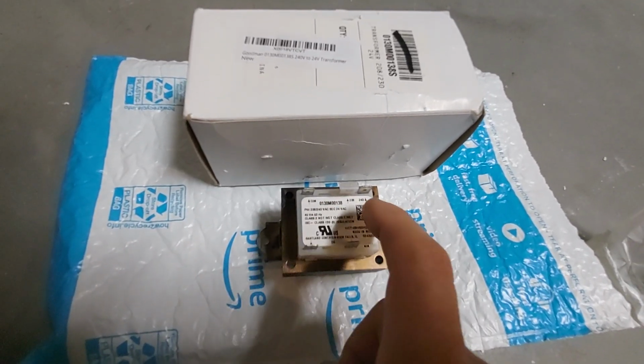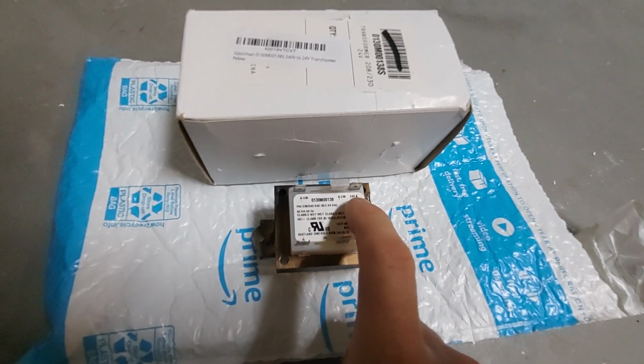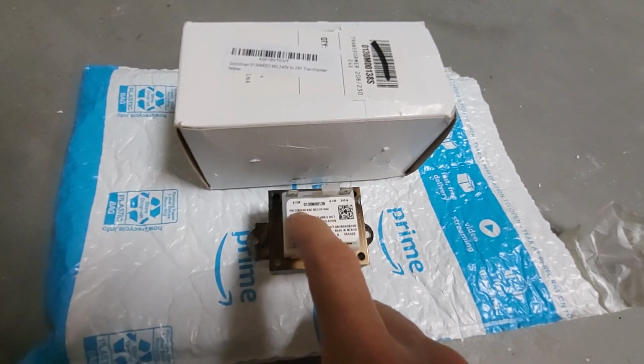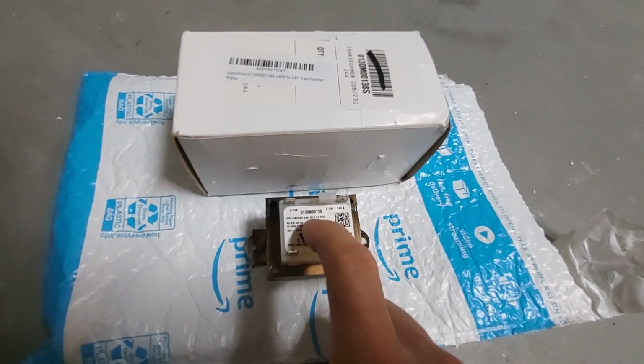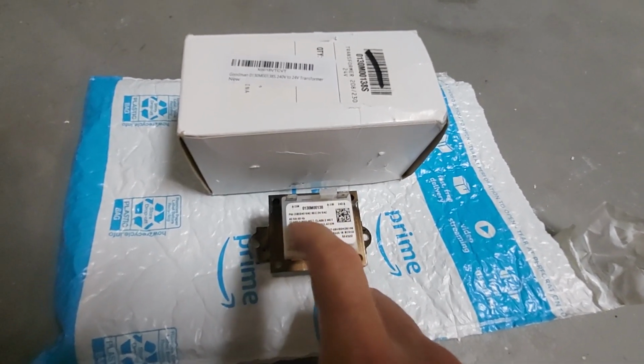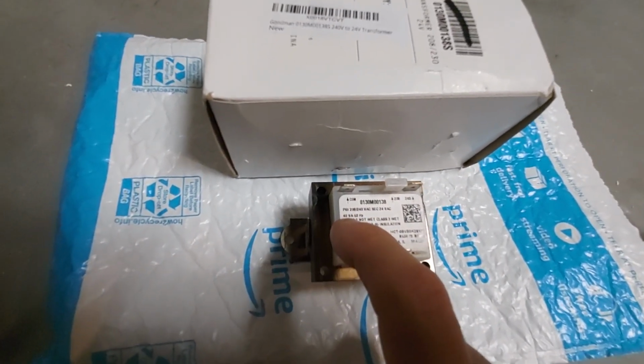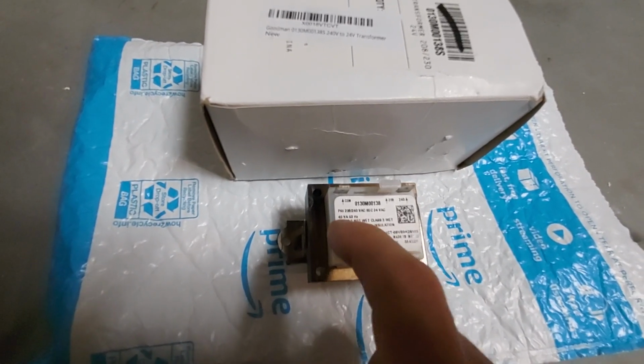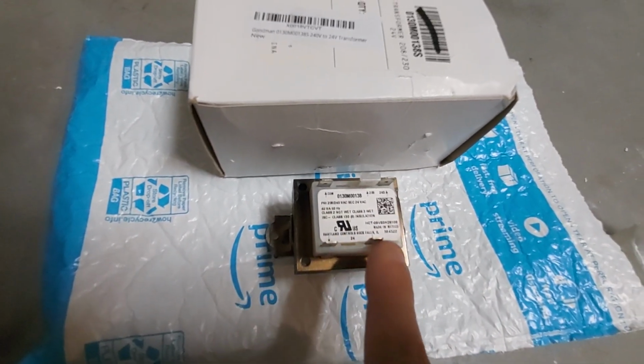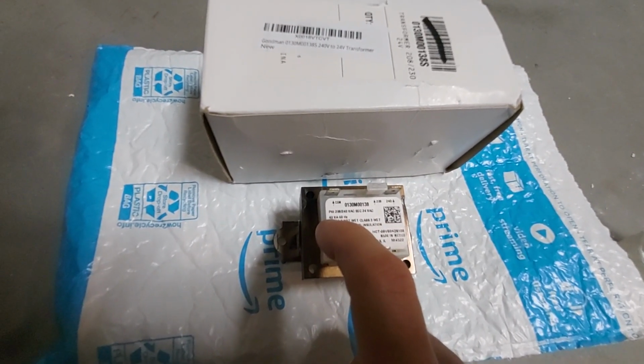Like I said, you have to match up the input, which is 230 to 240, and you have to match up the VAC out, that's the 24 volts. There's also another value here - it's 40 volt amp, make sure it says 40. That's very important, 40 volt amp. That's not the output of here. It has to be 40 volt amp, and it has to be 60 hertz for the US.